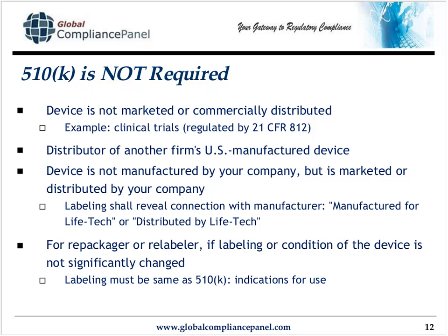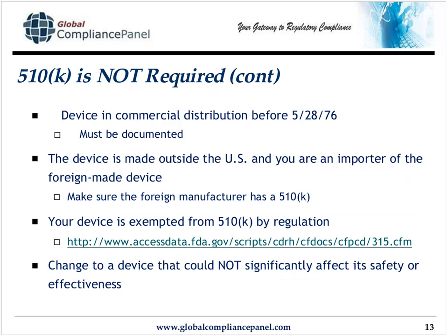For firms that repackage and relabel, contrary to the earlier examples, situations in which the labeling or condition of the device is not significantly changed. For example, the labeling is the same, no 510K is required. Also, if you have a device that's been in commercial distribution since before May 28th, 1976, the pre-amendments devices, as we call them, a 510K is not required.